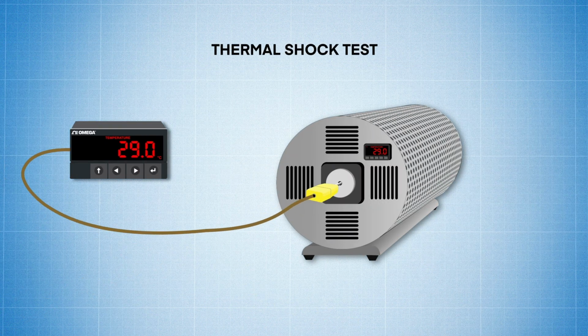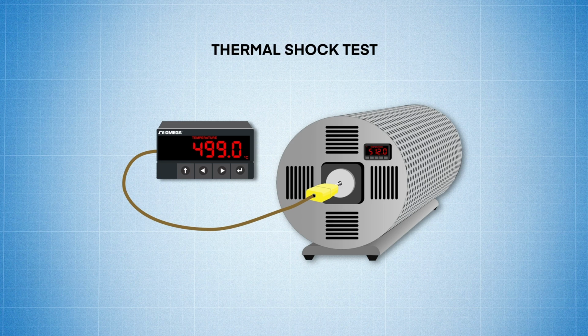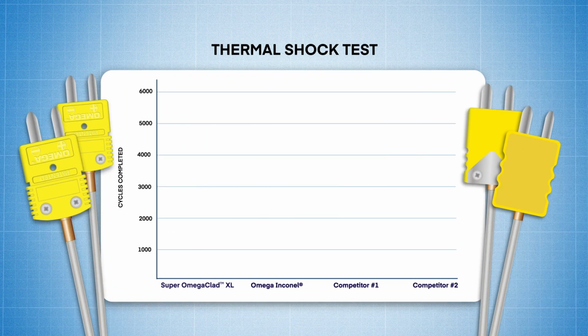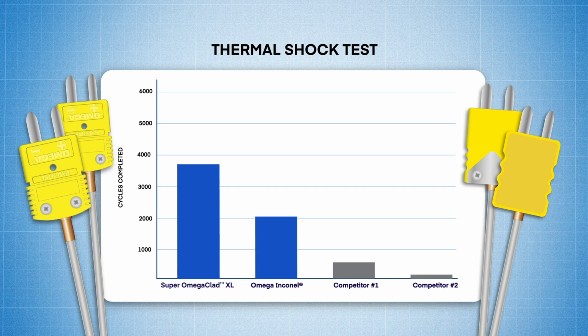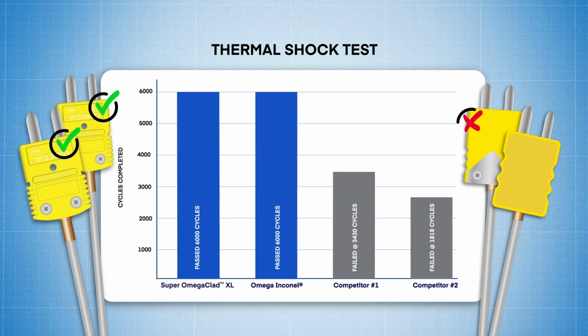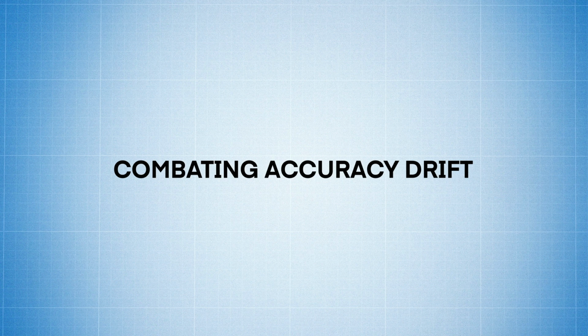For the thermal shock test, we cycled the temperature for each probe with a 20-second heat-up time from 29 degrees Celsius up to 1,090 degrees Celsius, and then a 40-second cool-down time back to 29 degrees Celsius. And after 3 punishing rounds at 2,000 cycles for each round, the Omega probes perform best in accuracy, durability, and consistency. As with any thermocouple probe, accuracy drift is the enemy.